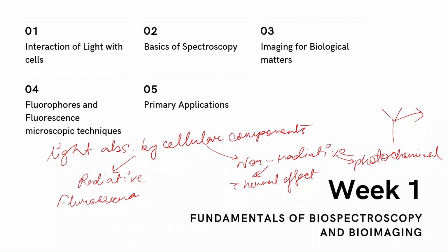Coming to the fluorescence microscope that most people use, it follows the basic epifluorescence excitation, and it utilizes filters and a dichroic beam splitter, which is essentially packed inside a fluorescence cube.